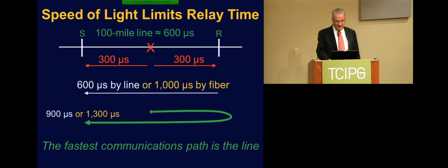Here's a 100-mile line between S and R - that's my end and your end. Let's put a fault right in the middle of that. If we say it's 100 nautical miles, then the speed of light is 6 microseconds per nautical mile. So by the time you and I know anything about that fault right there in the middle, the fault is already 300 microseconds old, 50 times 6.